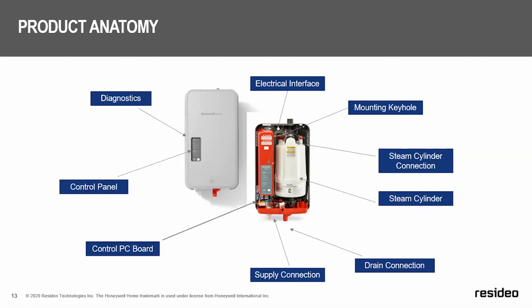Moving around from the top to the right, we have our mounting keyhole slot for easy installation. The cylinder connection, which is done with a rubber connection and hose clamp. The steam cylinder, of course. The drain and the supply connection. Inside that red enclosure, that electrical behind the interface, will be the circuit board. The control panel is visible, showing you on the front side through the cover, along with the diagnostic LED outputs.